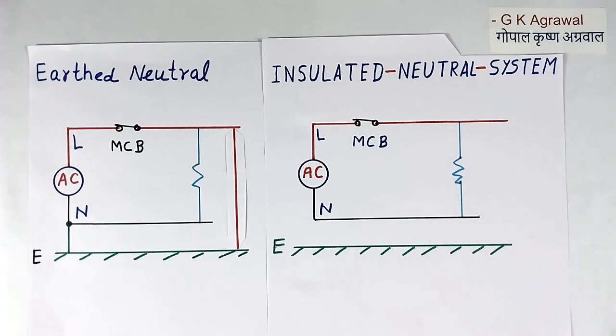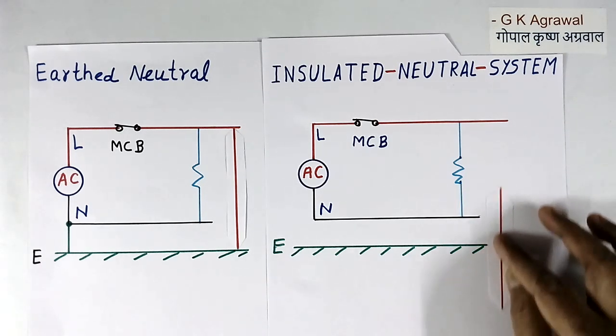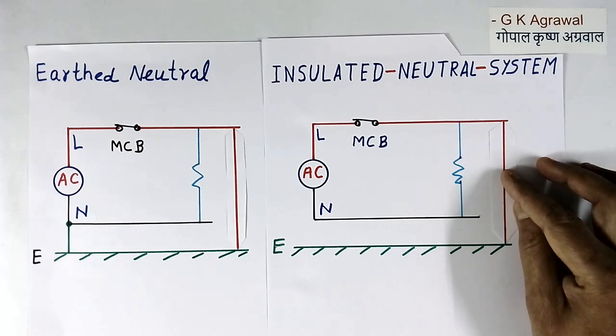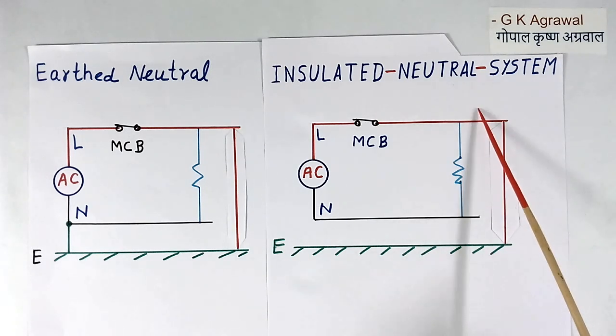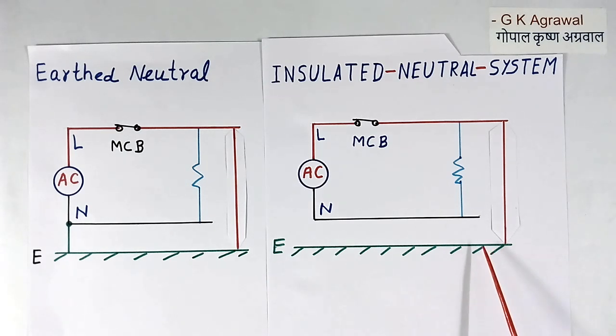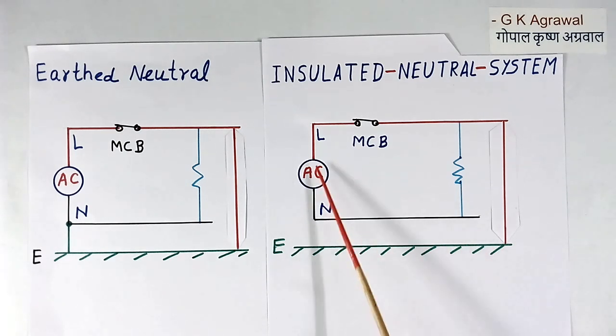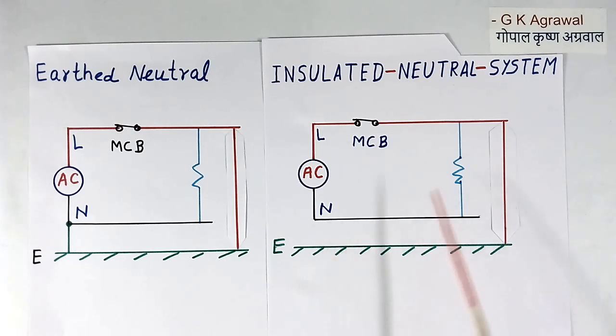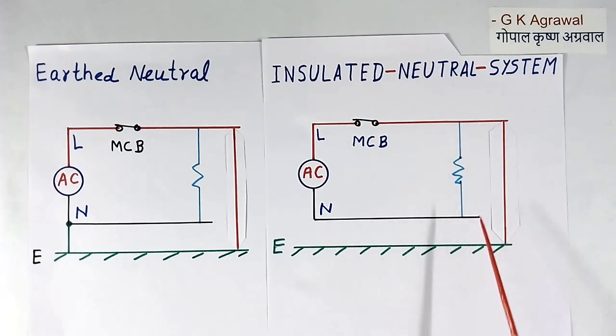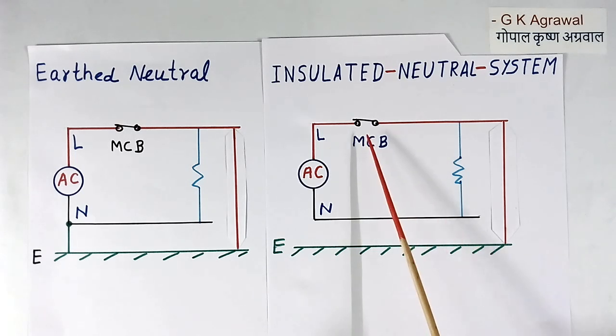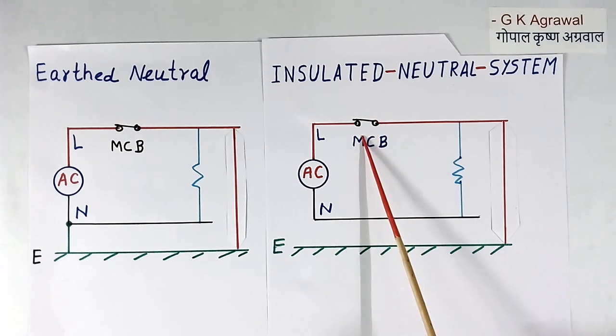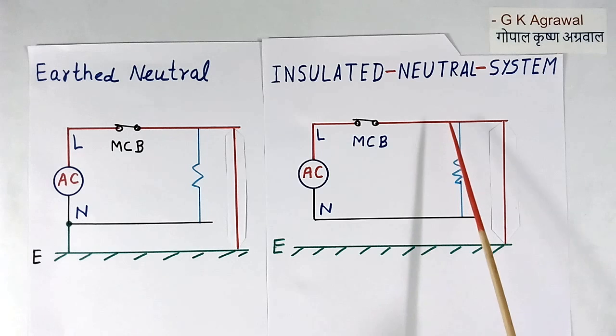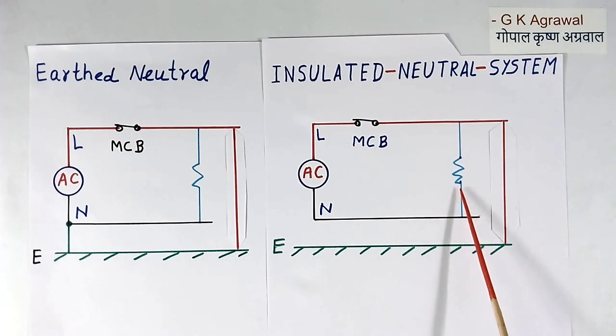In the insulated neutral system, suppose there is also a short circuit between line and earth. But here, current will not flow. There is no return path, so current will not flow due to the short circuit. As current will not flow, the MCB will not trip, and we will continue to get AC supply across the load. The load or equipment will continue to work.